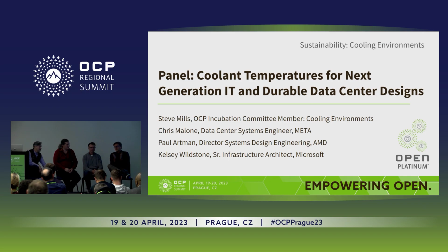This is a trade-off that we look at all the time. How much trim chiller do you need, for a particular climate, to hit 30 most of the time? And then these data centers are hundreds of thousands of square feet. So what is 30 C? There is going to be variance on the data center floor for a bunch of different reasons. So this is a big trade-off that we look at.